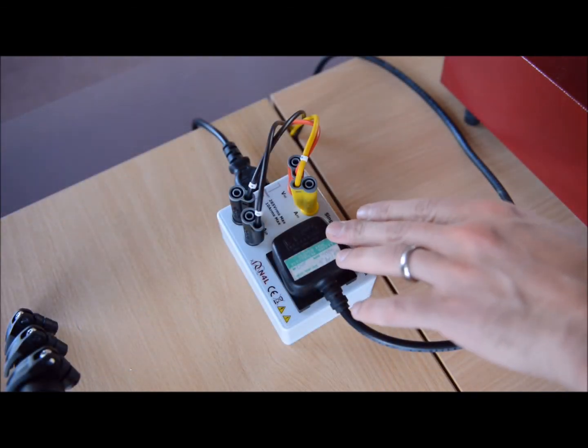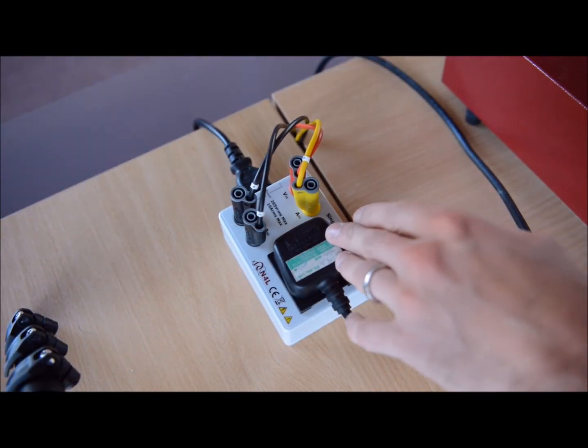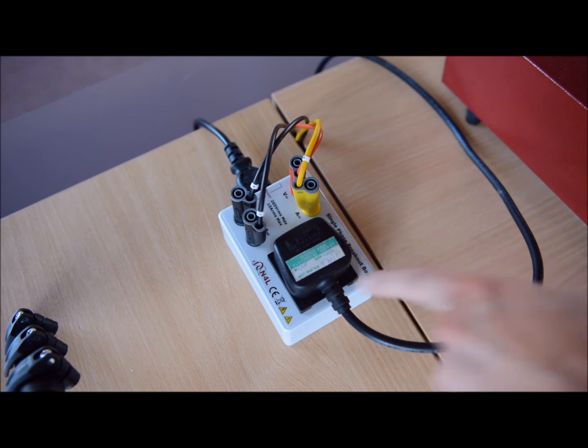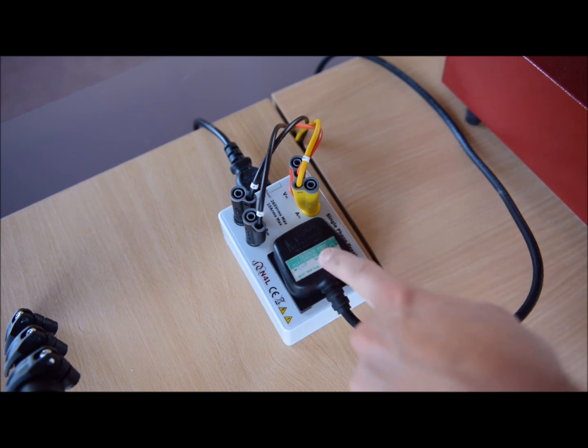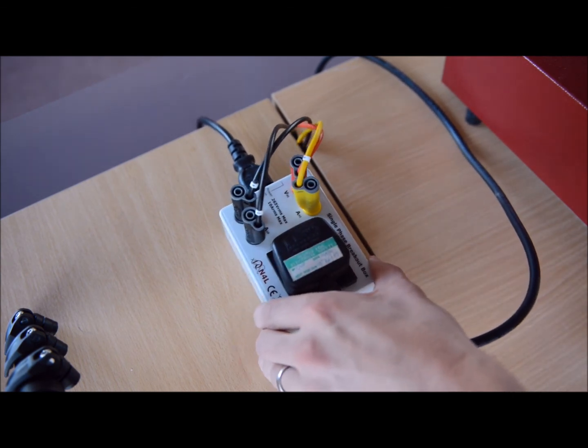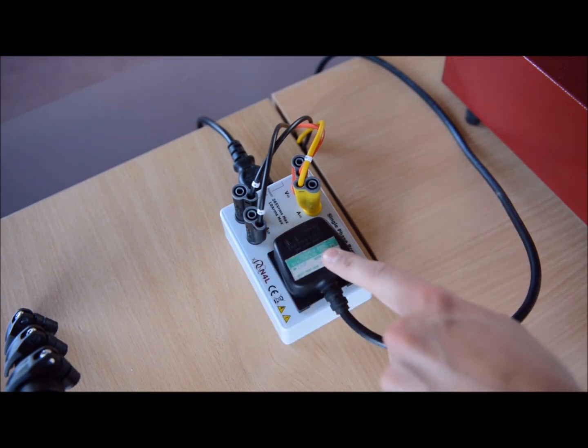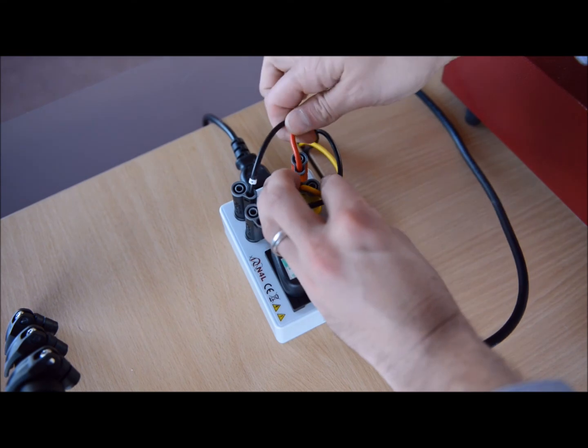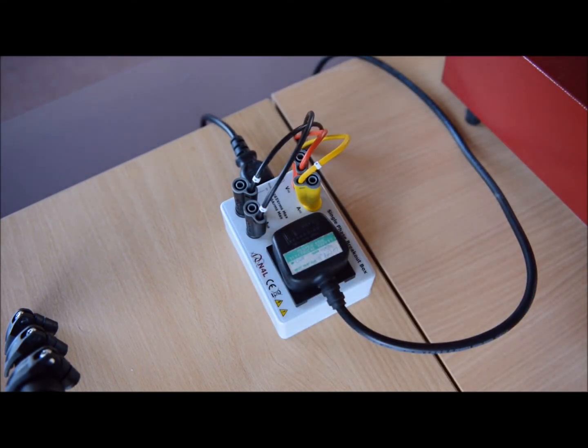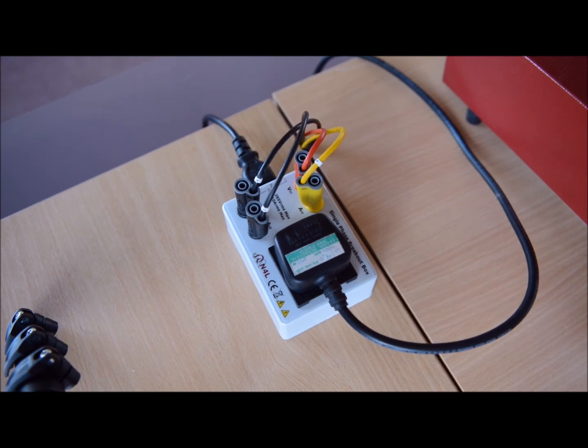So here is the point where we measure the input of the AC drive. What we've got here is a breakout box. This is an N4L designed breakout box and makes it very convenient to take out the voltage connection, which we can see here, and to take out the current measurement just there. And we're using the internal shunt on the PPA1500 power analyzer. It just makes a very convenient and safe method of measuring input power to the device.